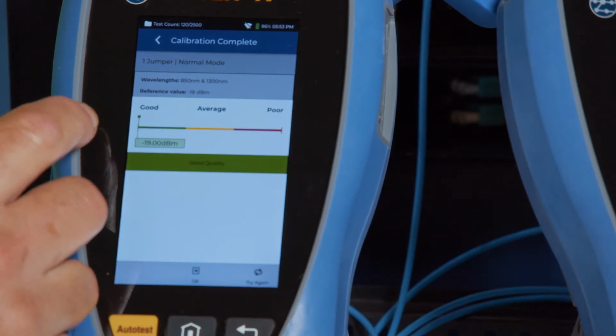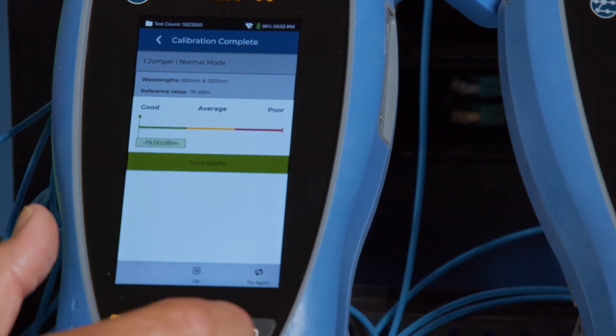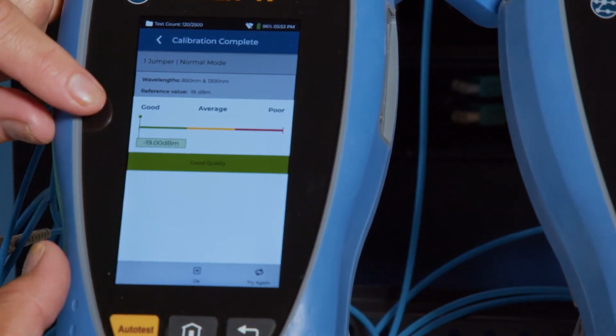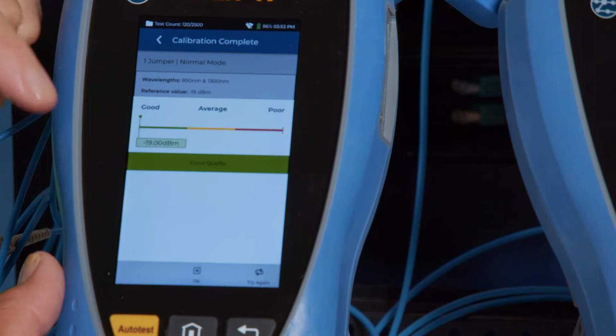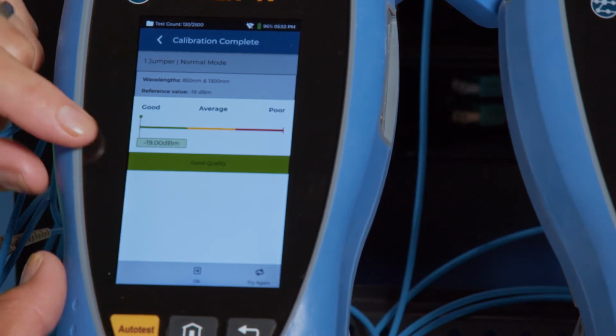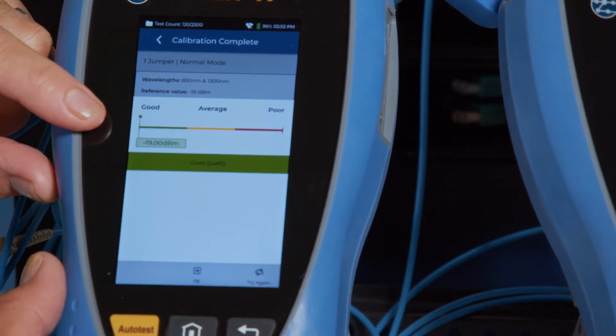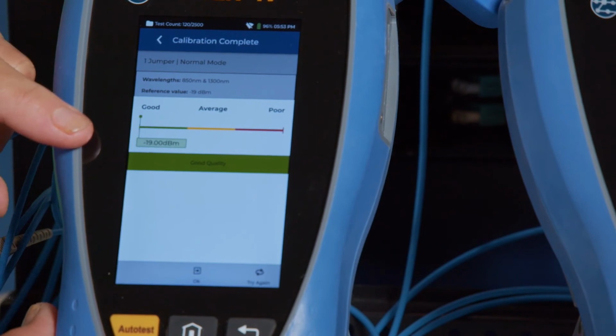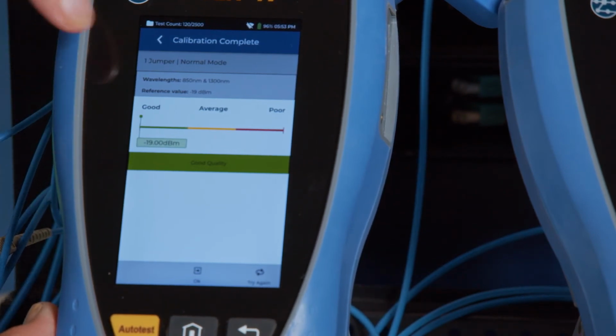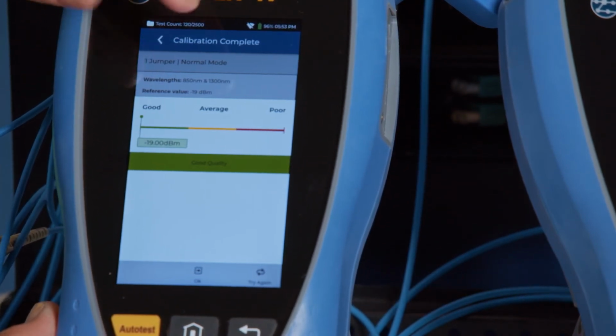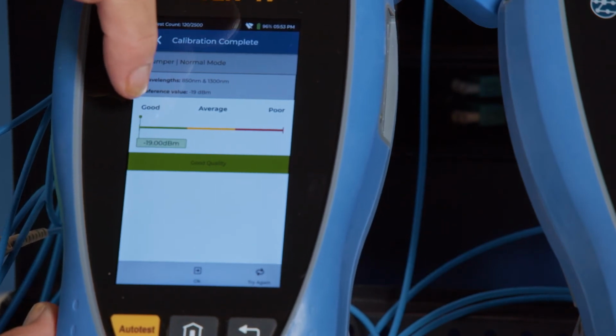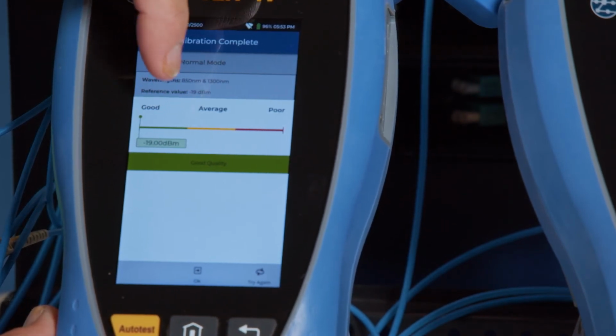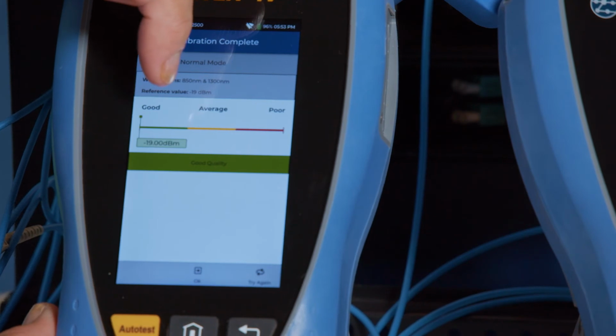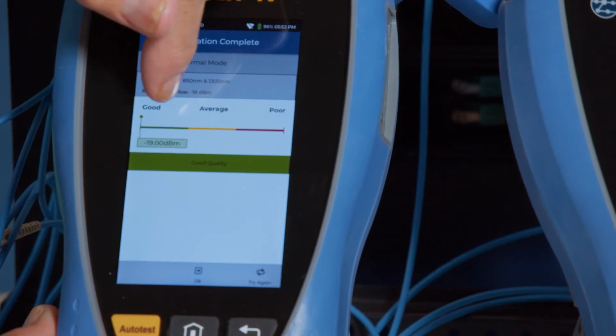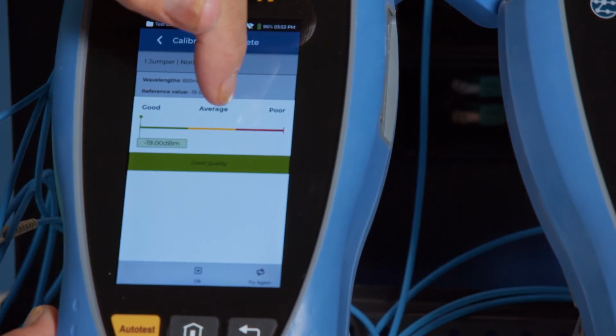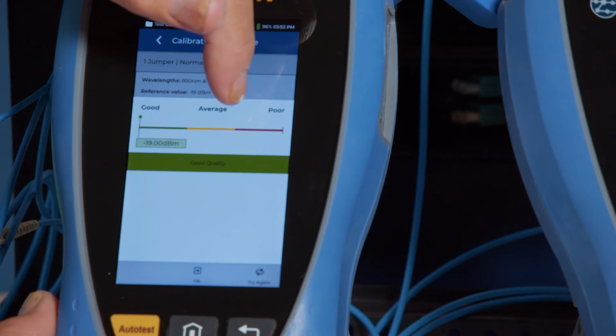And the reference value is shown on the screen here, and it gives us the power that was measured at the end of the field calibration or set reference process, which is minus 19 dBm. So we know that the power output is good because it's in the green section. If the connectors are dirty, we'll start to see that power drop, or if the cables are bad or have any damage, we'll see that indicator drop down to a point where it's getting into the red.